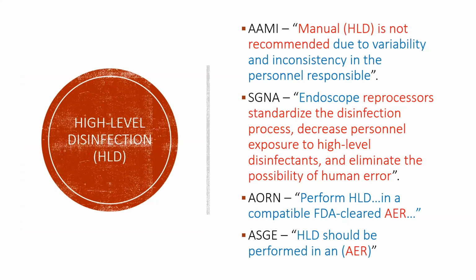All organizations speak to the preference for and value of automated processing, especially to allow standardization and limit the human error element. When it comes to high-level disinfection, AAMI has focused statements against manual disinfection. Manual guidance is given, but automated processing is promoted. They promote that manual guidance should be reserved as a backup option only for when automated processes fail.